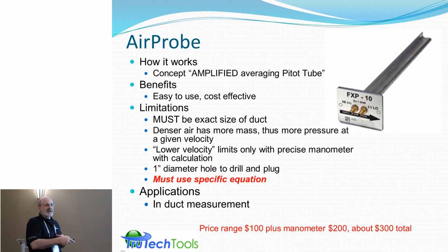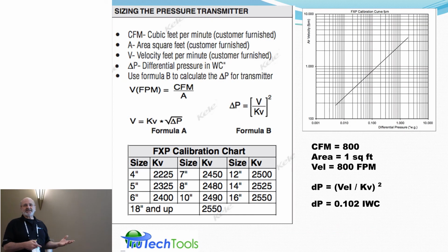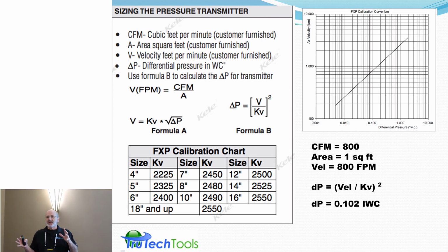You need a precise manometer to get the low end readings on its scale. And you must use a specific equation. I'll show you that equation here. This looks like, hey, great, it's linear, but it's actually logarithmic. With those tubes, you have to make sure you have so much straight duct before and after that. Absolutely. I didn't mention it here, but you're absolutely right. You can't have turbulent flow because you're going to get those dead zones, et cetera.